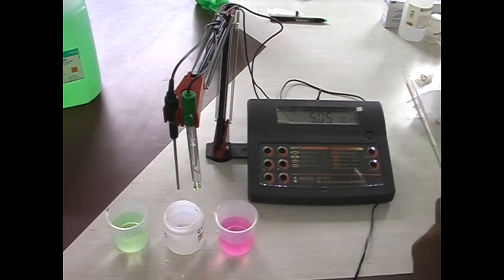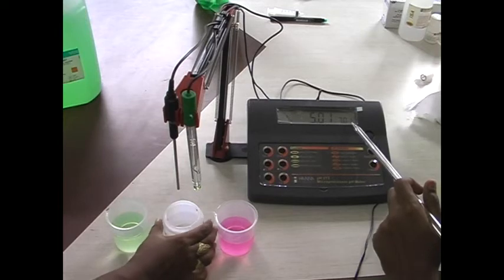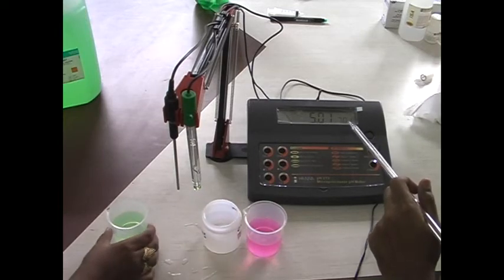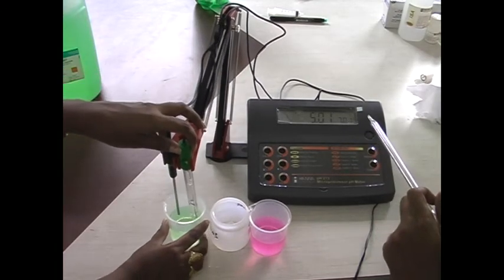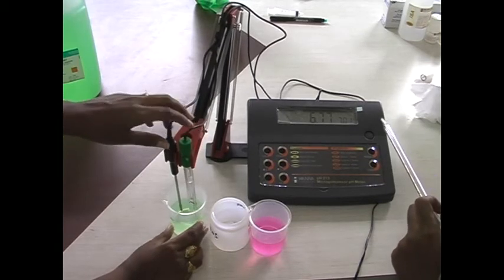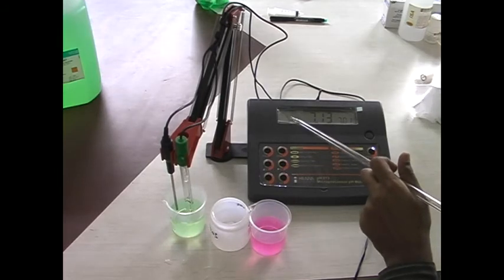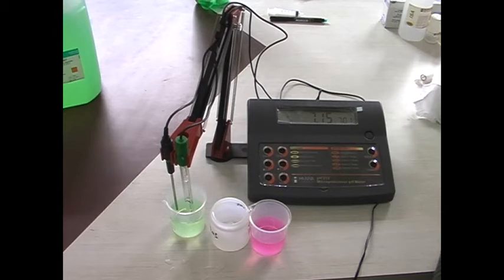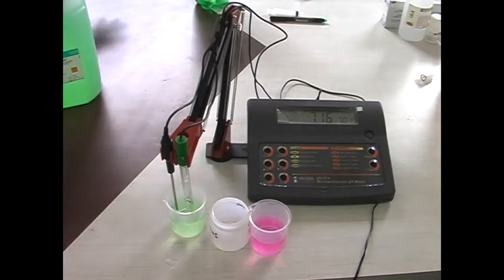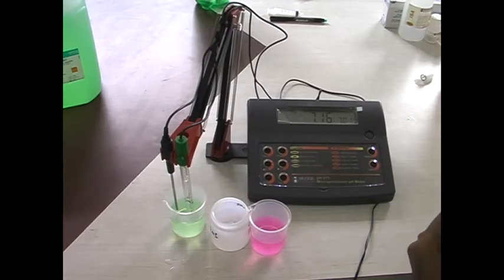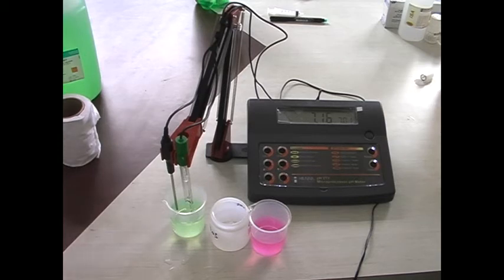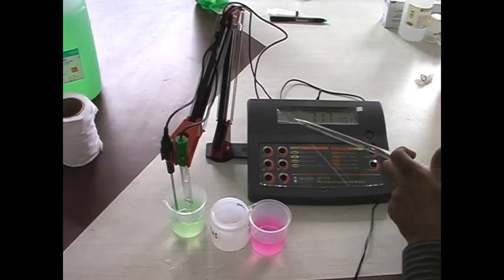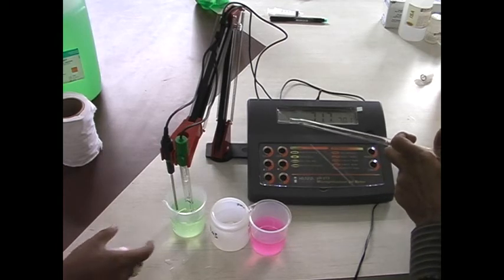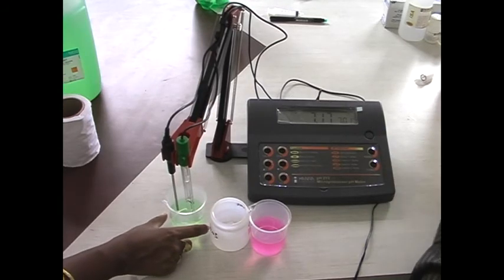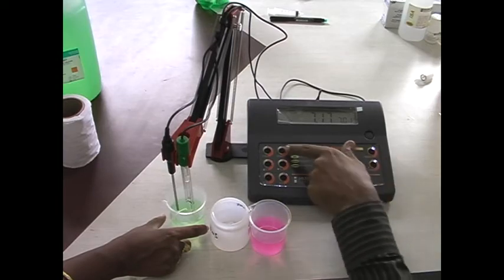Now you can see the display. On the primary display it is showing the current measurement, and on the secondary display it is showing 7.01. At this time you just dip your electrode and the temperature probe in the 7 buffer solution. Now the instrument is getting calibrated. You can see this hourglass symbol. Now just see the display. The instrument is showing CFM and the ready indication. It means that you just need to confirm this value. To store this 7.01 value, please press CFM.